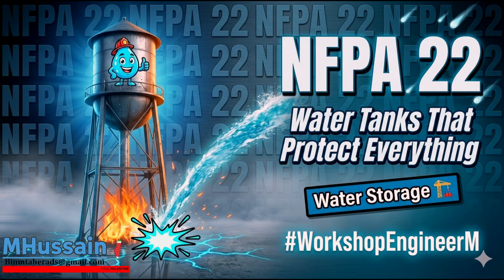Let's unpack everything we've analyzed today and synthesize the core takeaway for the safety engineers listening. If we look at the totality of the 2023 edition of NFPA 22, the prevailing theme is a fundamental shift in perspective. A water tank is not a static architectural feature. It is not just a concrete box or a steel bucket sitting dormant on a hill. It is a highly dynamic, rigorously engineered machine. It must manage complex thermal loads, resist extreme structural forces, control violent fluid dynamics, and mitigate biological and chemical decay. It may sit completely silent for 30 years, but it must spring into flawless mechanical action in milliseconds the moment a valve opens.